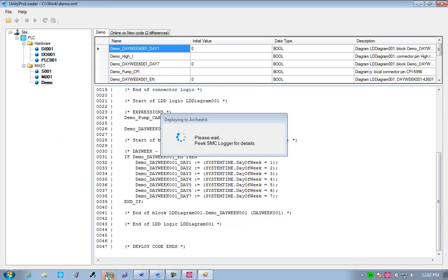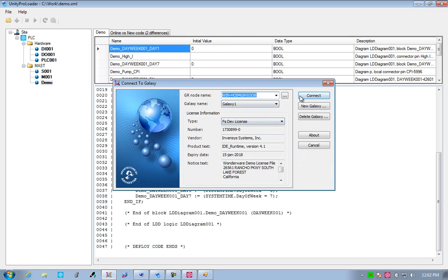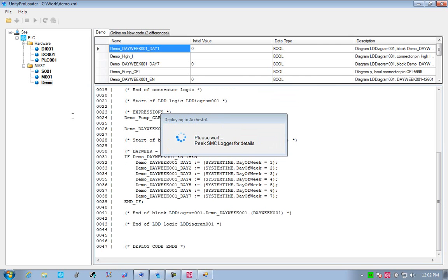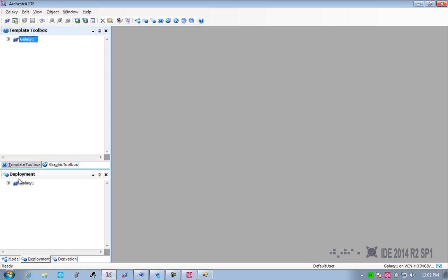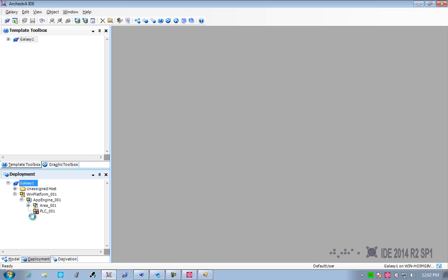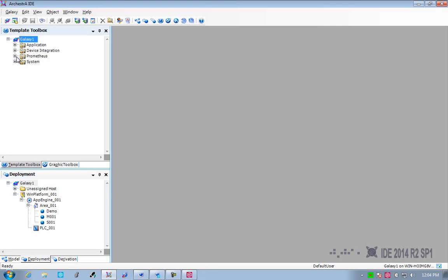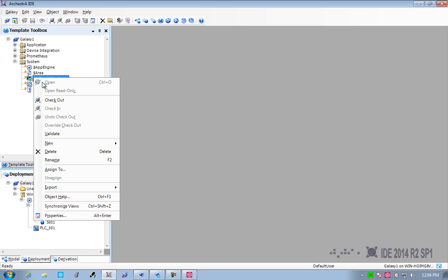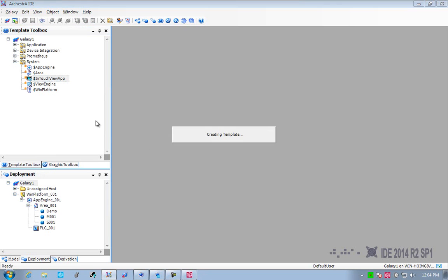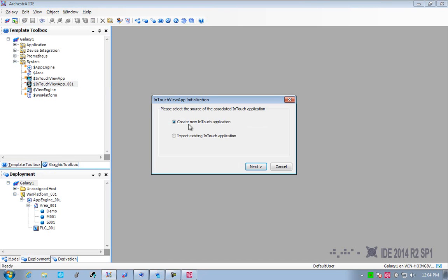Once the controller's up and running and the code's being parsed correctly, the loader will go on and now update ArchestrA. It's going to go and make instances of ArchestrA objects for us, and it's going to connect it to the physical IO in the controller. The cool thing about that is it's also going to create the DI object, it's going to configure the DAS, and it's going to create all the relationships directly into the code. Because it's been configured from one location, we don't need to configure this interface. We know that the symbols in ArchestrA or the ArchestrA objects are bound intimately to the logic. We don't have to test that. This means we can now commission directly from the HMI screen. We don't have to commission from the PLC code. In fact, we don't even need to see the PLC code to complete the process.